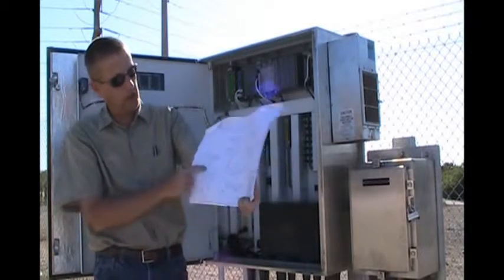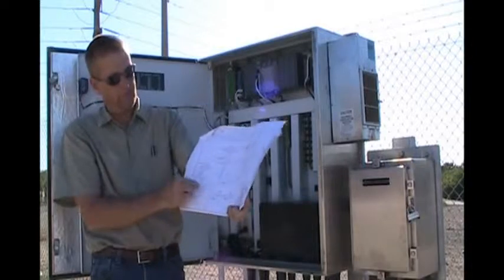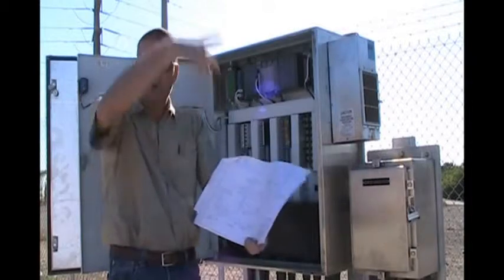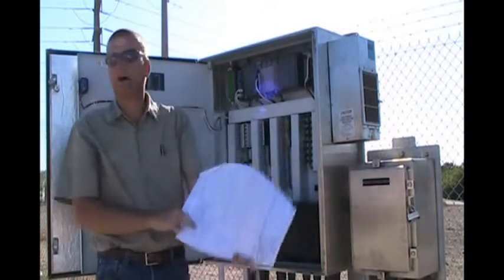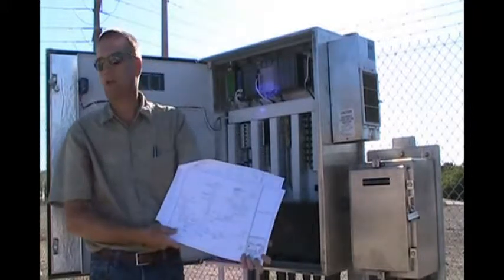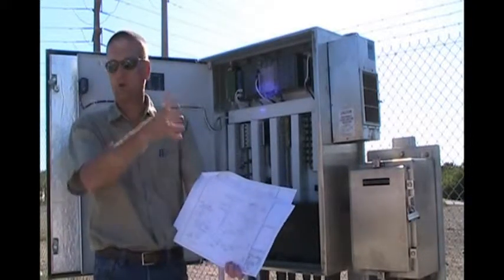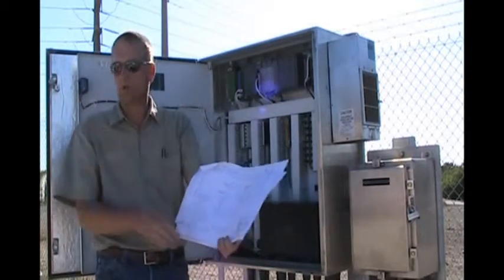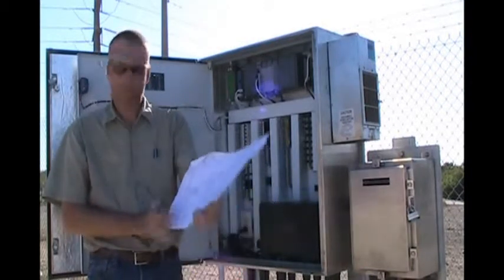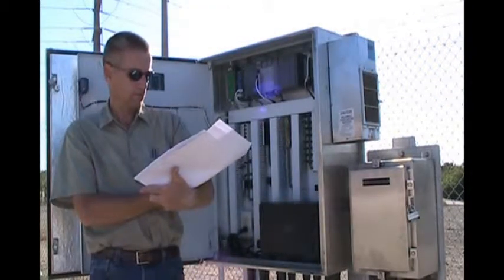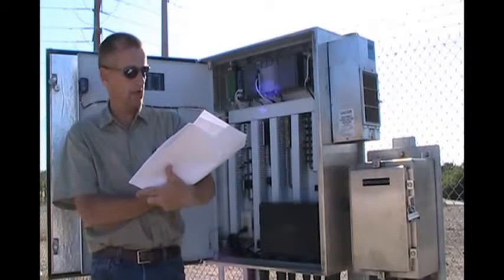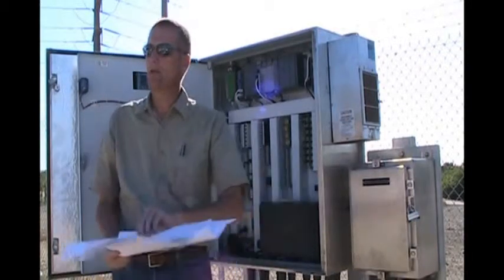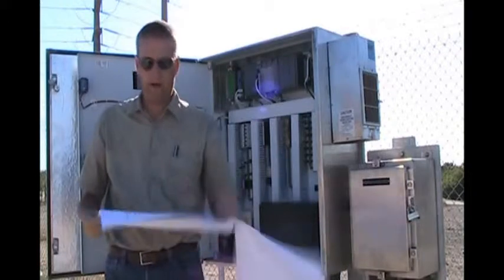So in here you have the Phoenix card, and then you'll have the wiring, which includes the polyphaser for the lightning protection, the ground, and then to the antenna. One thing about the Phoenix radios is they're a matched set. You replace one end, you have to replace both ends. So if you lose the transmitter, you have to replace transmitter and receiver on Phoenix radios. You can't replace just one. And this one's only using one analog signal and one digital signal, I believe is what it was. It's for the level and one for the intrusion into that panel down there.